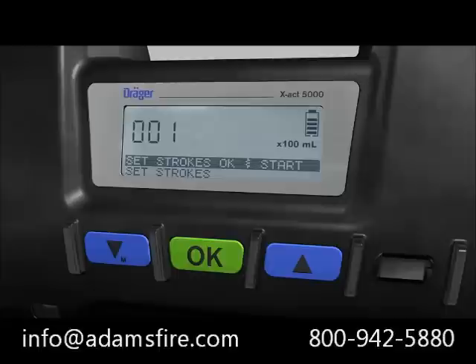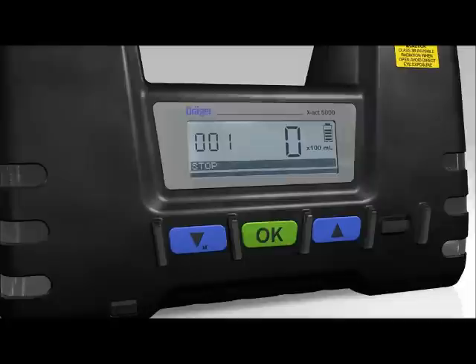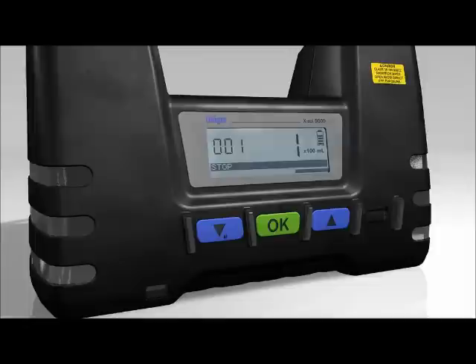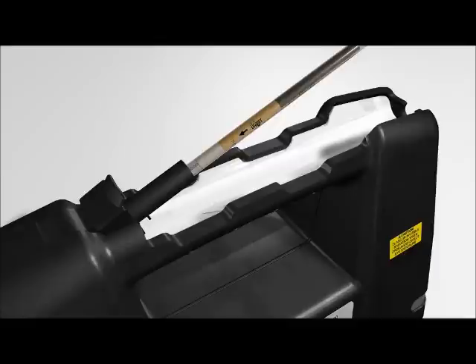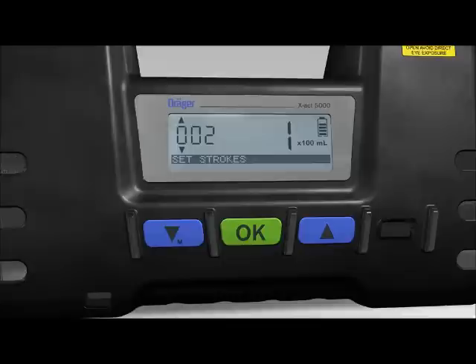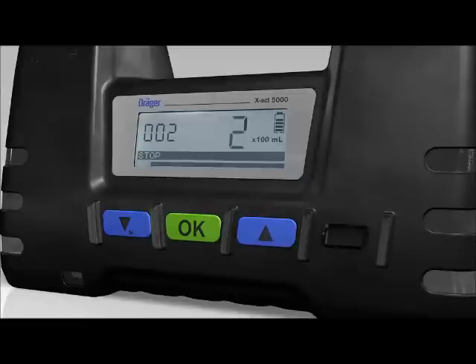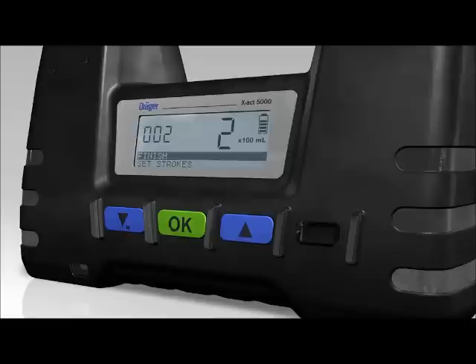The message STROKES OK and START appears in the matrix display. Press the OK button to instruct the Dräger X-act 5000 to start measuring. Once measuring is complete, the LEDs flash green; the tube shows the concentration by changing color. You can now finish the measurement or continue using the same tube. To continue, change the number of strokes manually and press OK to start measurement. Once complete, remove the Dräger tube.